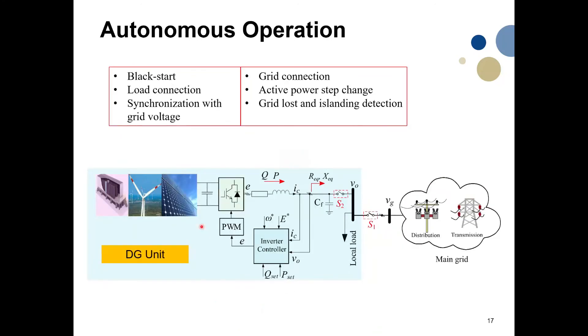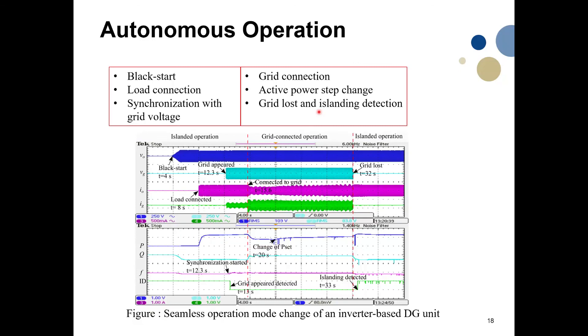We tested the autonomous operation of the system. The setup uses a programmable DC voltage source that can emulate any renewable energy source. We tested different operations: black start, load connection, synchronization, grid connection, voltage change, and power change — covering all aspects of seamless operation.